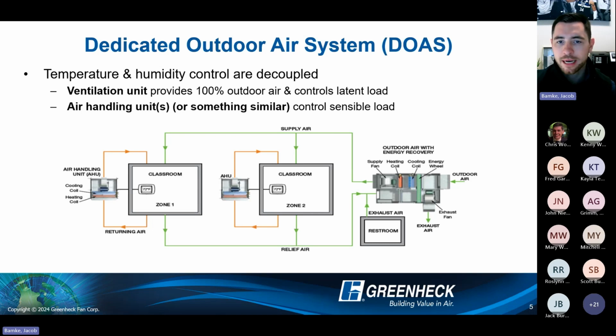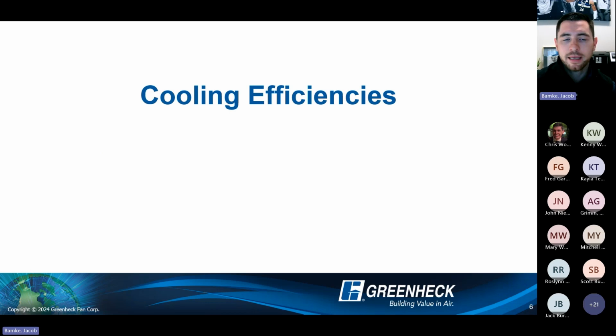So it's providing it 100% outside air, distributing it to each individual space, and then something downstream will handle that temperature, that sensible load. This gives you really precise outdoor air delivery, so you're not overventilating the space, but it also gives you really precise temperature control as well. So temperature, latent or humidity, and your outdoor air percentage are all controlled precisely with a true dedicated outdoor air system application. And where we're going with this is, obviously in a school, for example, I talked about education facilities, you might see one of these systems, or each of these systems, in one school. And the biggest piece that changes is the cooling efficiencies that you have to look at.